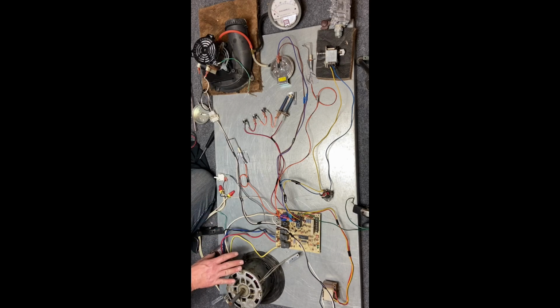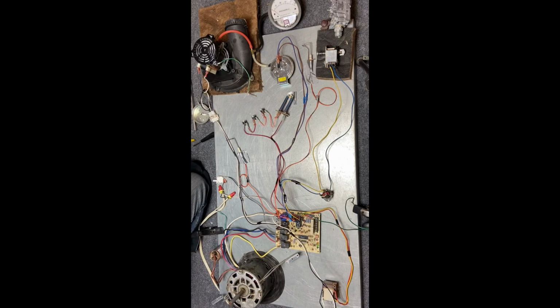Now we're going to take a look over here at the blower motor side. So next we're going to check the speeds on the motor. So if I check my unused speed, I have 0 amps, the top one. And if I check low speed, I have 0 amps. That's for my fan circulating. And if I check the heating terminal, I end up with 0 amps, so it's not working. And if I check my high speed, 0 amps. And if I check my common side, my neutral side, I also have 0 amps. So 0 amps means this motor should be working. If we look and see, the motor's definitely not working.